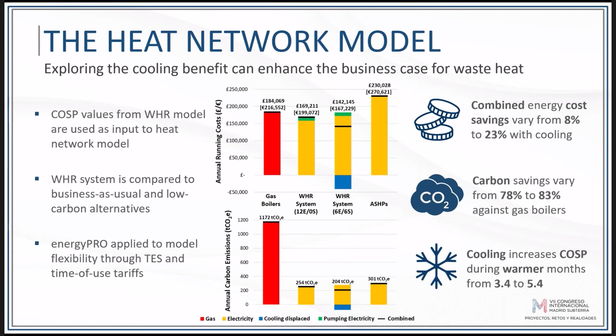To summarize the cost analysis, we modeled a number of scenarios, and here I want to highlight two: 12 months in extract mode, or a 50-50 operation. I want to highlight how waste heat is able to reduce the cost of decarbonization. Comparing to air source heat pumps, looking at the levelized cost of heat—effectively the NPV of the project divided by the total energy it provides over its lifetime—we see the system is able to reduce the levelized cost of heat by 9% against air source heat pumps.